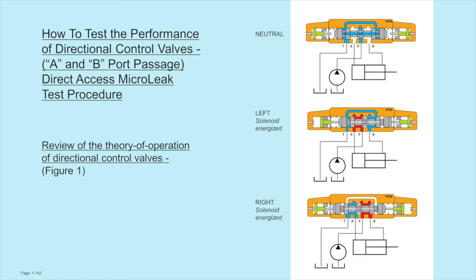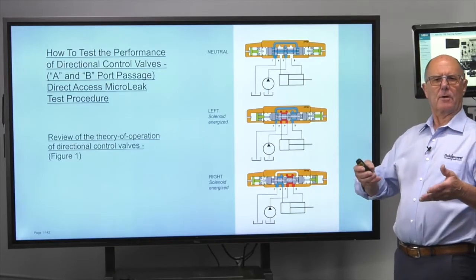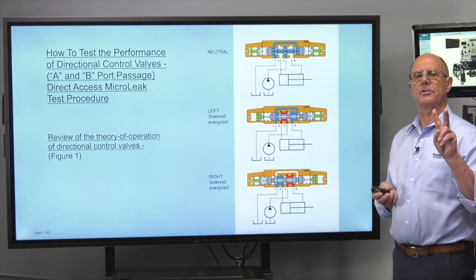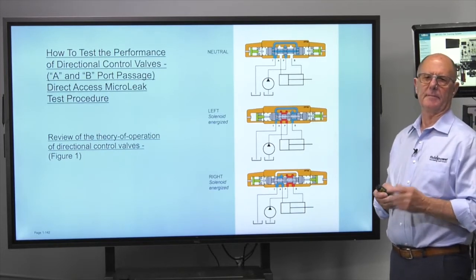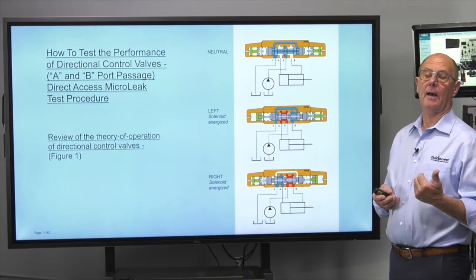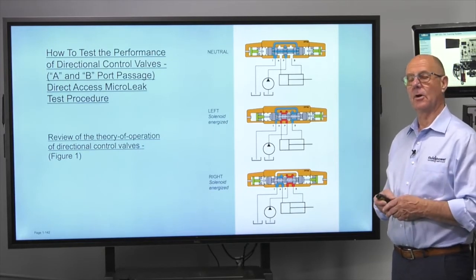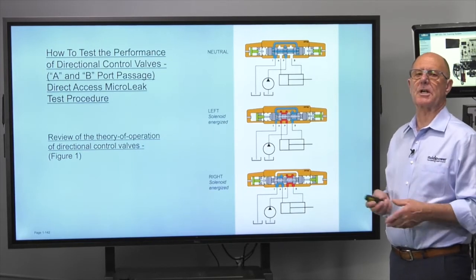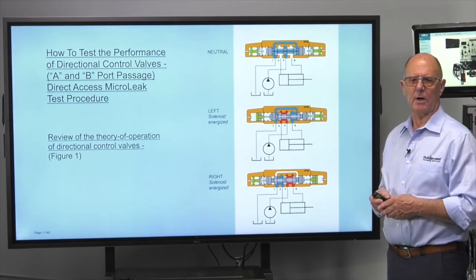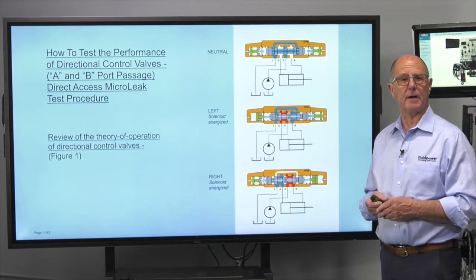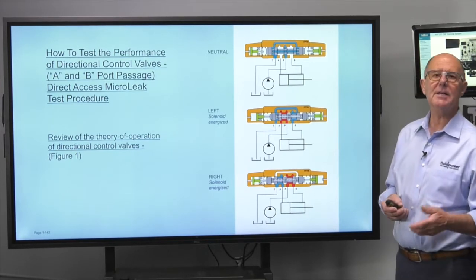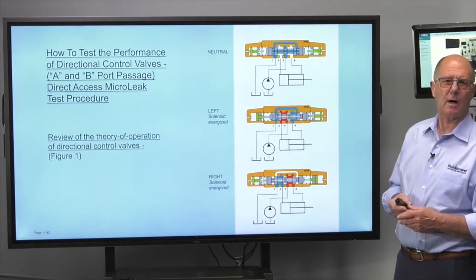If I have, let's say, a forklift, because if I've got a vertical downdrift on a forklift, there can only be two components which can cause the problem: the cylinder and the directional control valve. There are no more suspects than that. So we're going to focus on the directional control valve, which quite frankly is the easiest component to focus on.